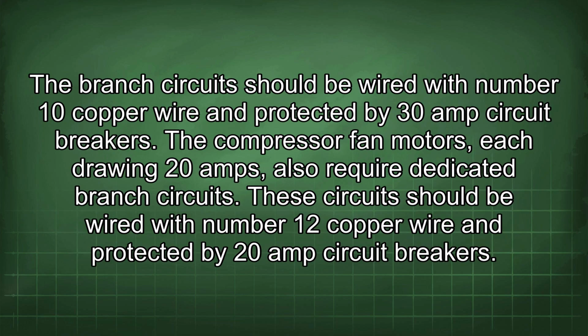The branch circuit should be wired with number 10 copper wire and protected by 30 amp circuit breakers. The compressor fan motors, each drawing 20 amps, also require dedicated branch circuits. These circuits should be wired with number 12 copper wire and protected by 20 amp circuit breakers.